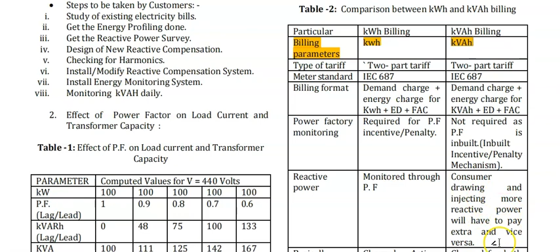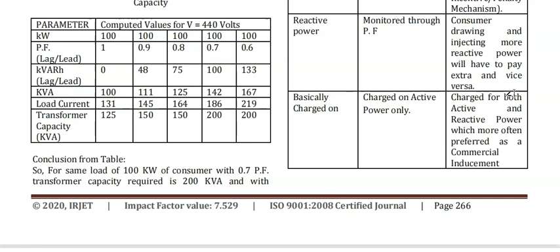Power factor monitoring: it is required for power factor incentives or penalty under kWh billing. It is not required under kVAh billing as the power factor is inbuilt. Under the incentive and penalty mechanism, reactive power is monitored by power factor, and a consumer drawing or injecting more reactive power will have to pay extra and vice versa. Basically the charge is on active power only. Under kVAh you are charged for both active and reactive power, which is more of a commercial inducement.